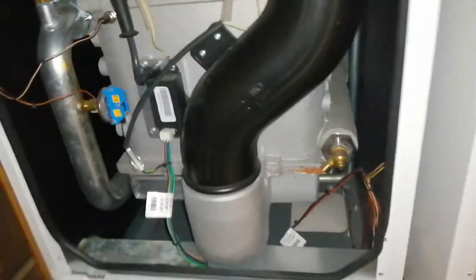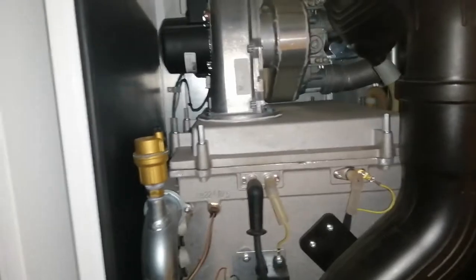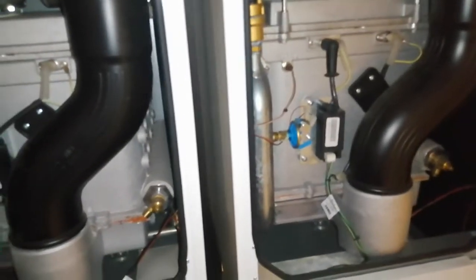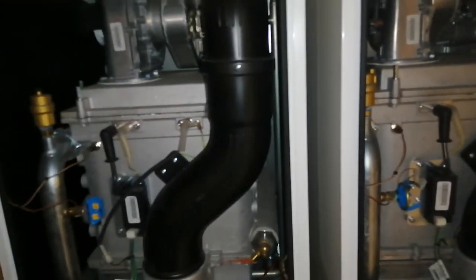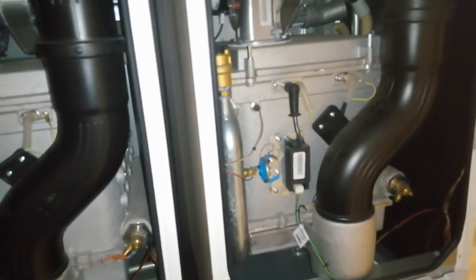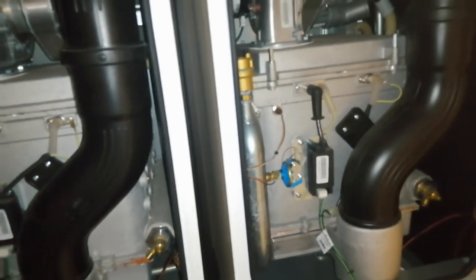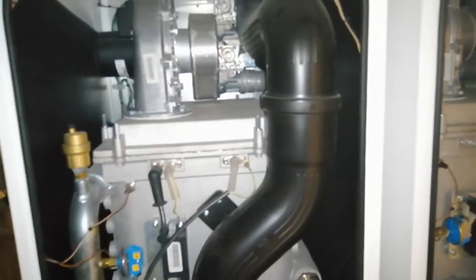Do your safe isolation. Look for your safety mat underneath the control panel. Notice how this control panel doesn't have a safety mat underneath it, so you should enter with even more caution when you go into this sort of control panel, and make a note of it for the site supervisor that there is no safety mat underneath the control panel, because there should be one there in the event of being electrocuted. Ideally in your tool bag it's good to carry a few plasters and so on. You might not want to carry a full first aid kit, but it's good to have some plasters or things in there that can stem a serious cut, and so on. I don't want to go too deep into health and safety, but just bear some of that in mind, because accidents will happen.